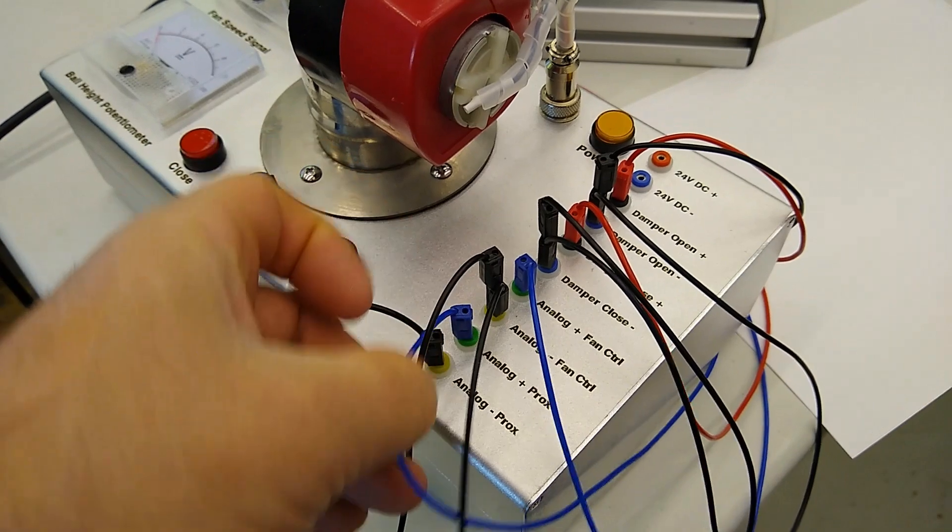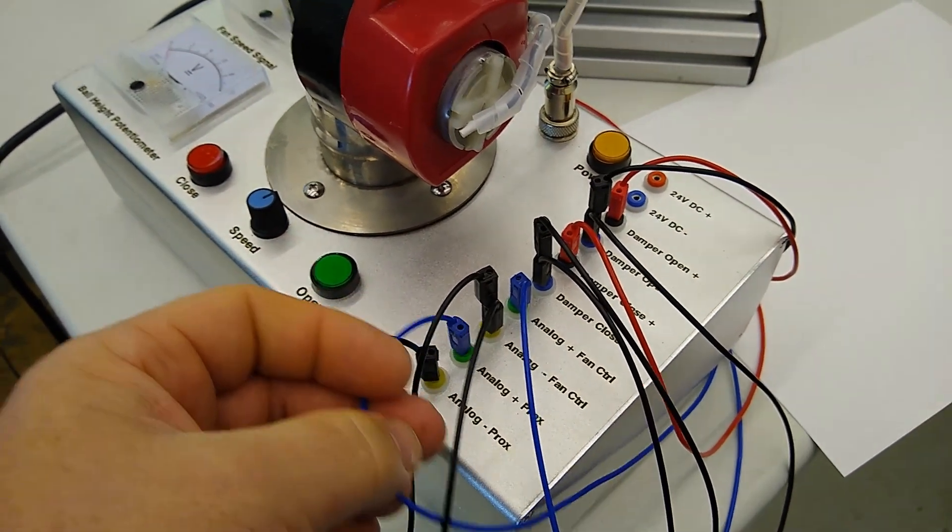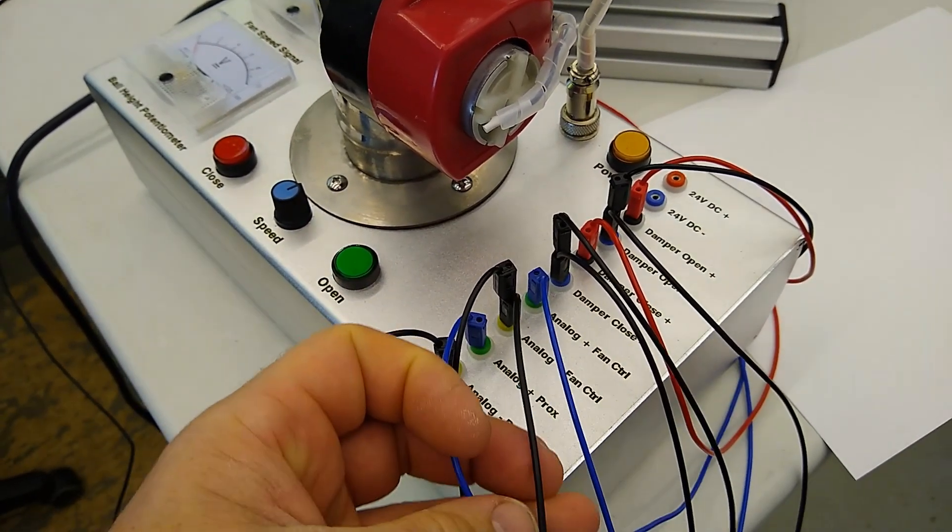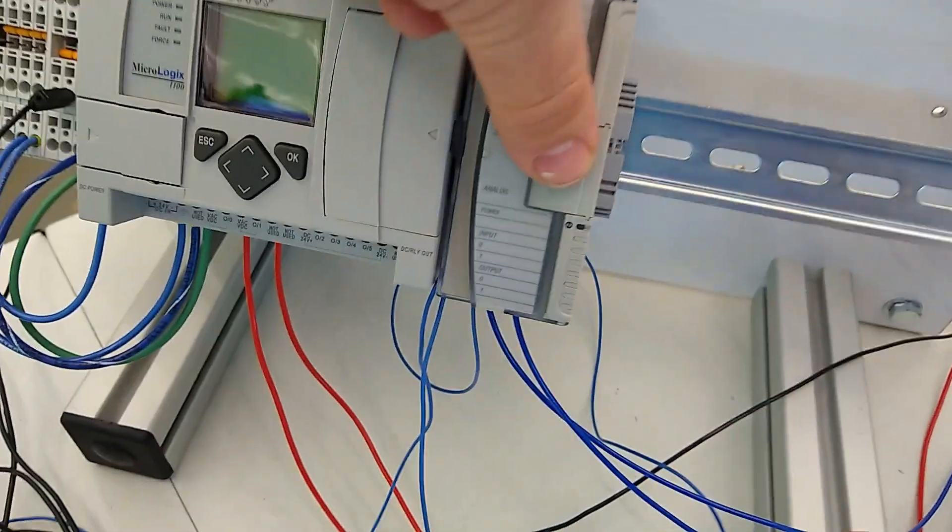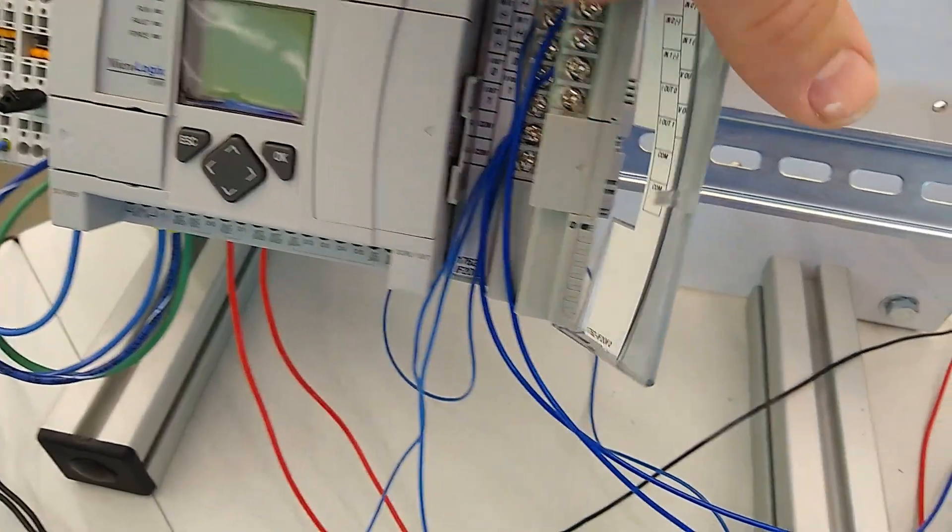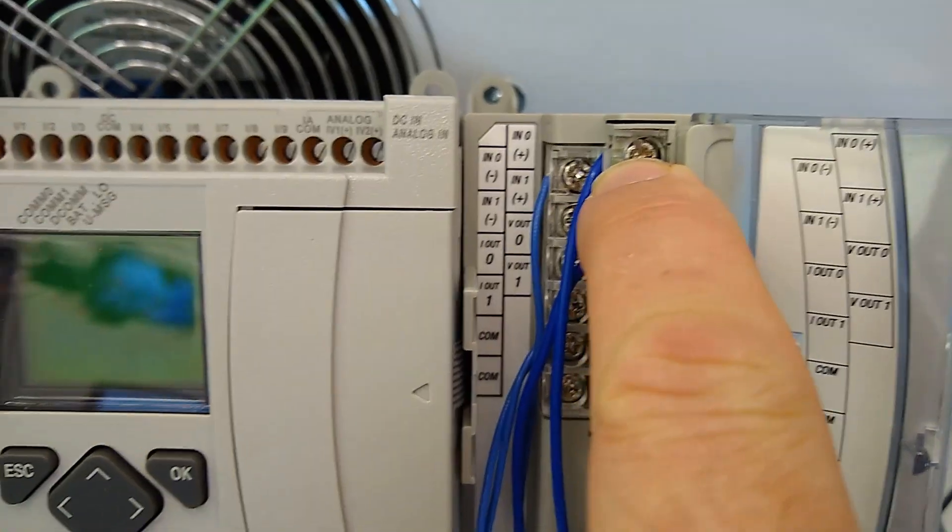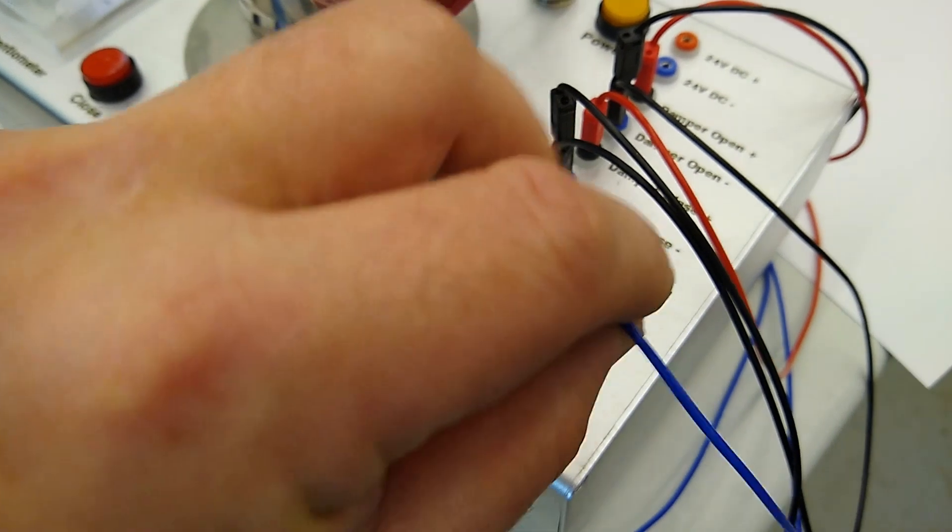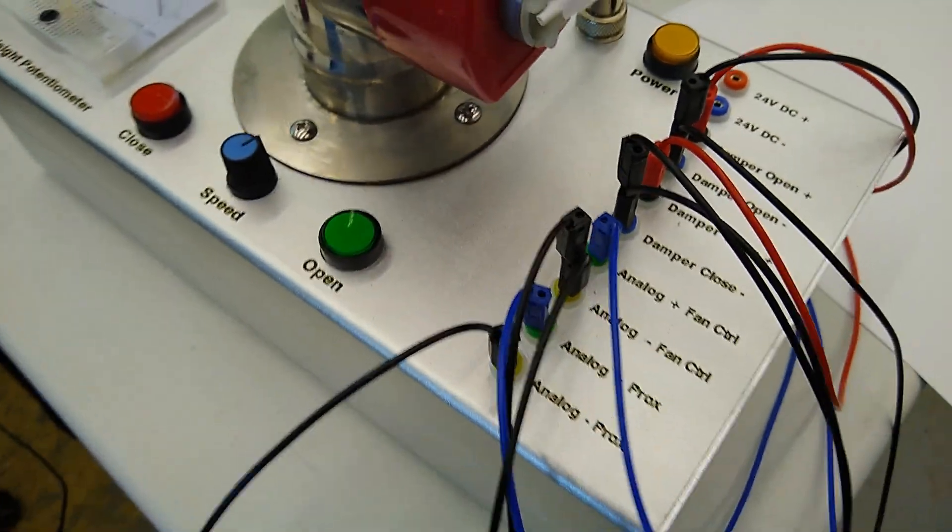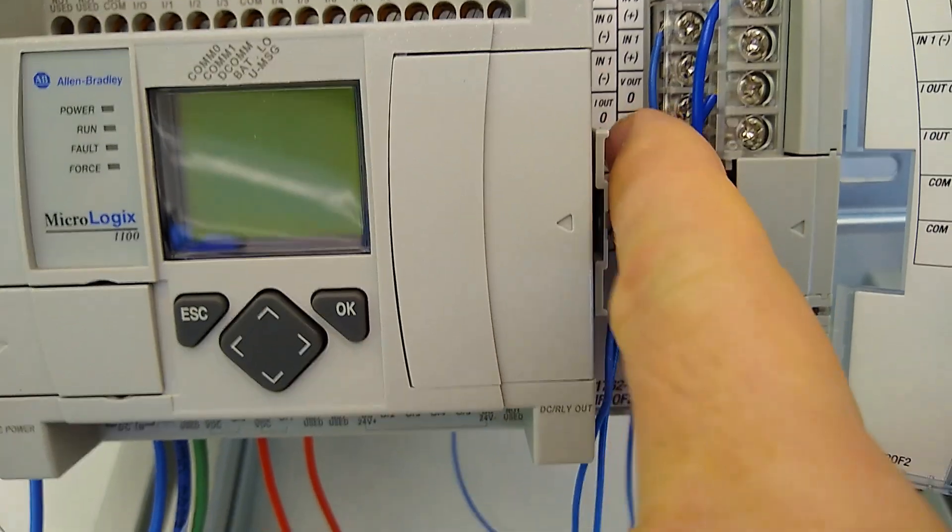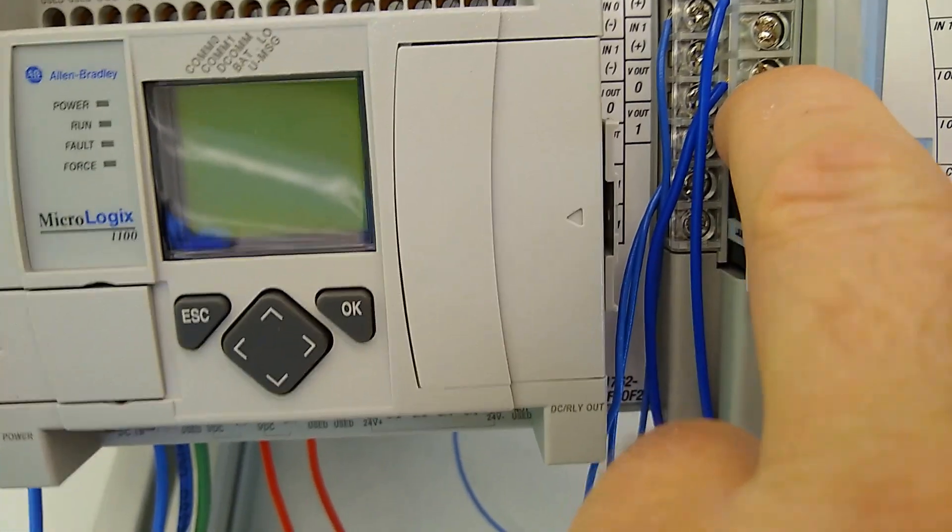And then our analog PROX PLUS is going to go to input zero of our analog. So we pop open our 1762 IF2 OF2. It is going up here to the IN0 PLUS. Then our fan control PLUS is going to go to output zero of that analog, and that will be VOUT0, which is right here.